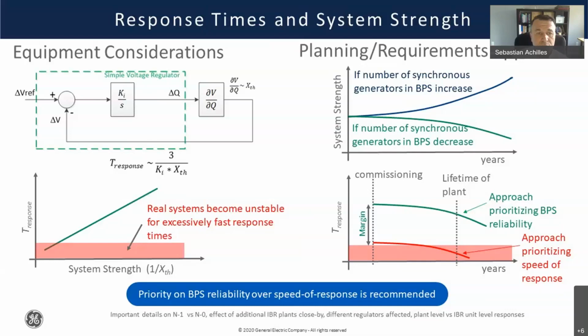This derivative of voltage with respect to reactive power can be thought of as the system reactance. Depending on how much reactive power is injected and the system reactance, there will be a modification to voltage that feeds back into this voltage regulation loop. So this is a simplified version of a real voltage regulator.